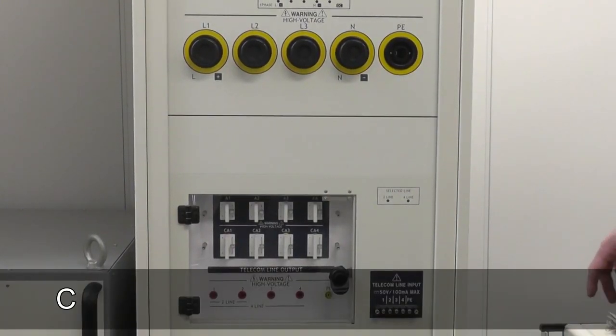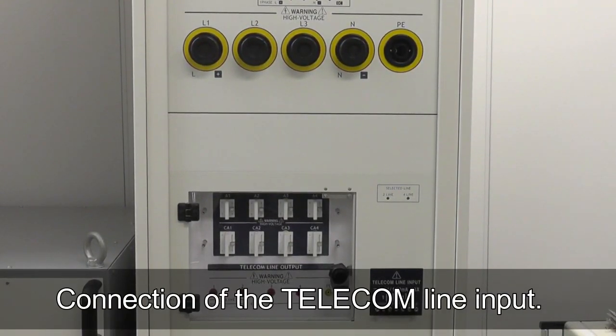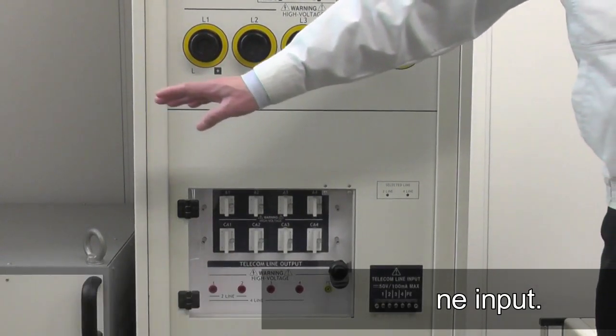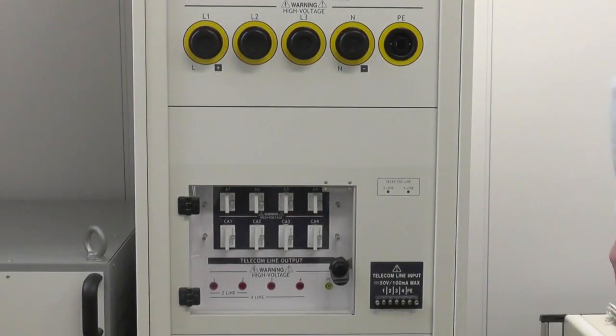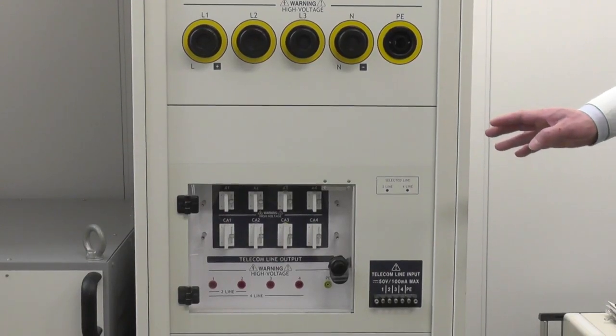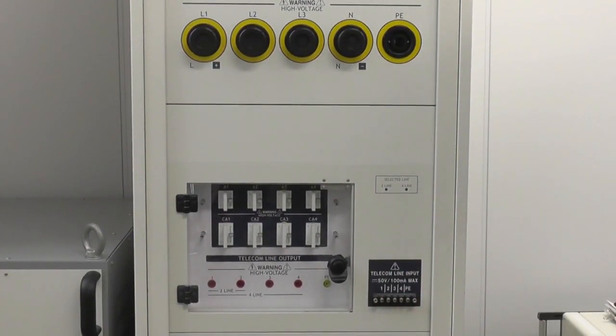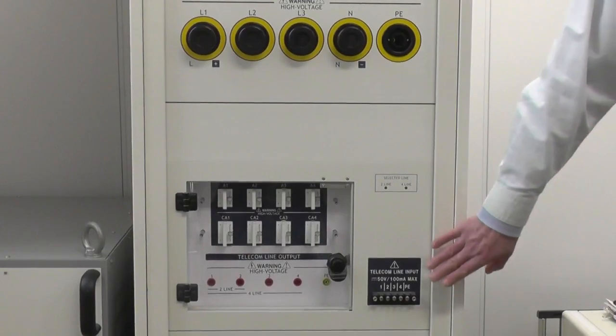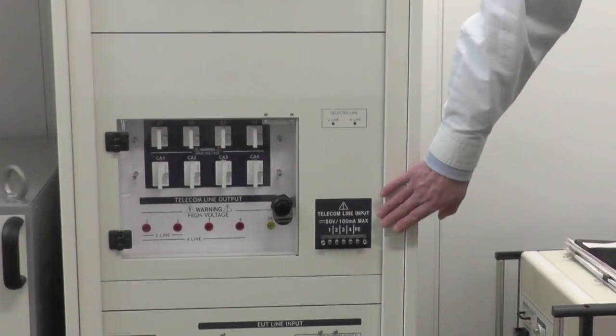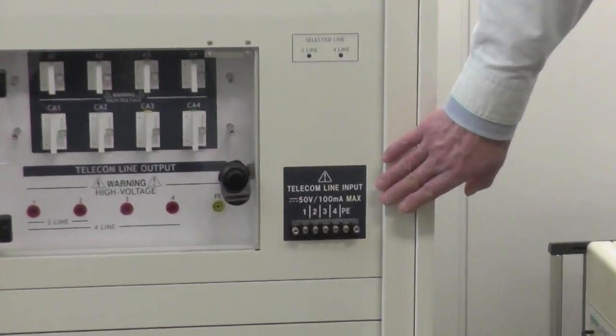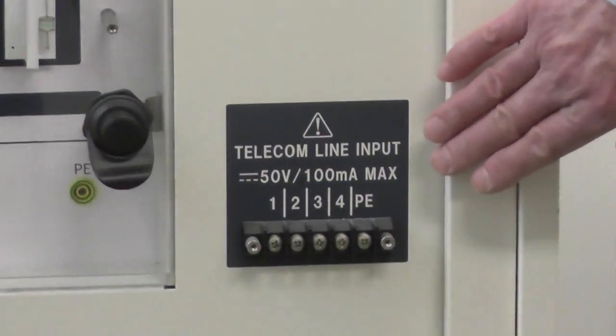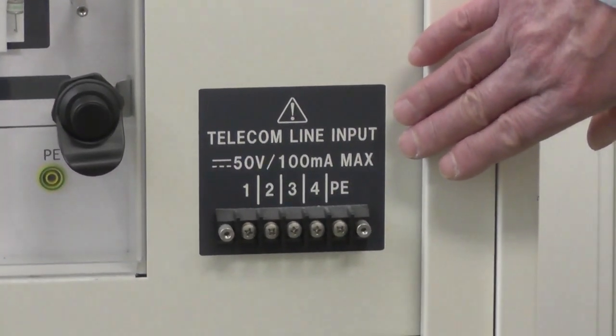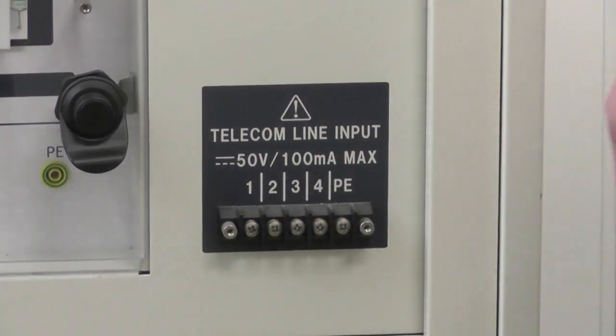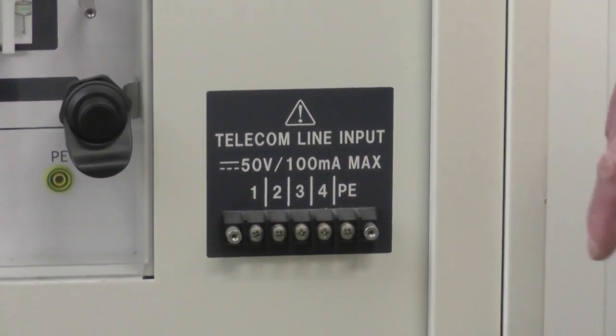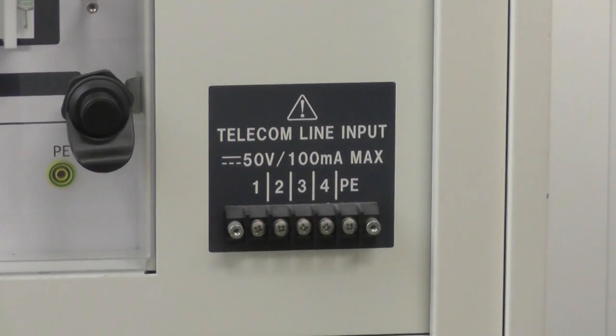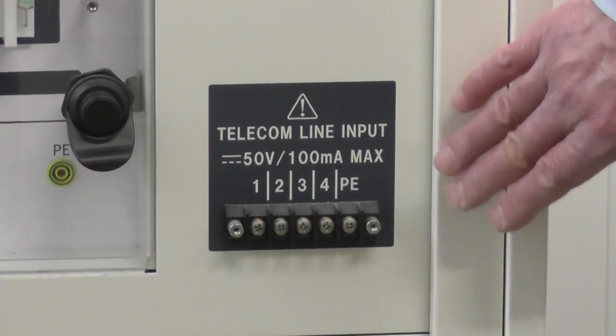Now the telecom line input connection. Be sure to check that the power supply to the EUT is shut off, and the lightning surge simulator is also in the off state. Here are the input terminals for inputting signals from auxiliary devices to the EUT. Connect terminals 1 and 2 for a 2-wire system, and connect all 4 lines for a 4-wire system.